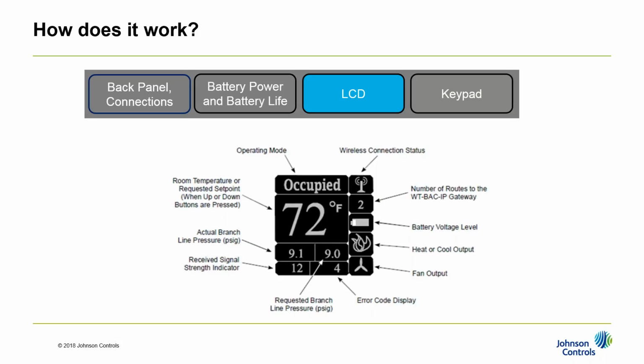First, there's the operating mode, which tells you the current state. It will either be in shoulder mode, a night setback mode, unoccupied mode, which is a looser range, or occupied mode, where you're doing full control for an occupied space.